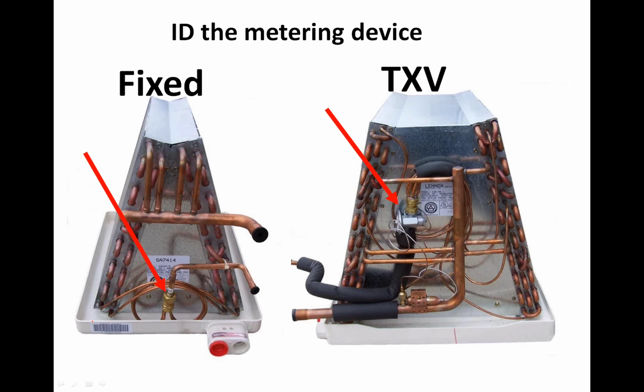If you were on an exterior mount on the suction line, like the bulb actually came out of the cabinet and outside, we want to make sure that bulb was well insulated so that the ambient air wouldn't have an impact on the reading. So those are just some things when you're looking at these things, we need to know what we have.